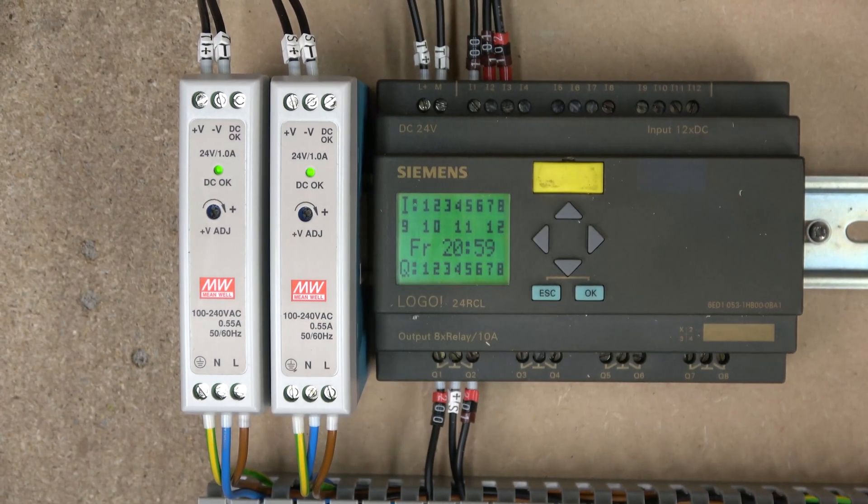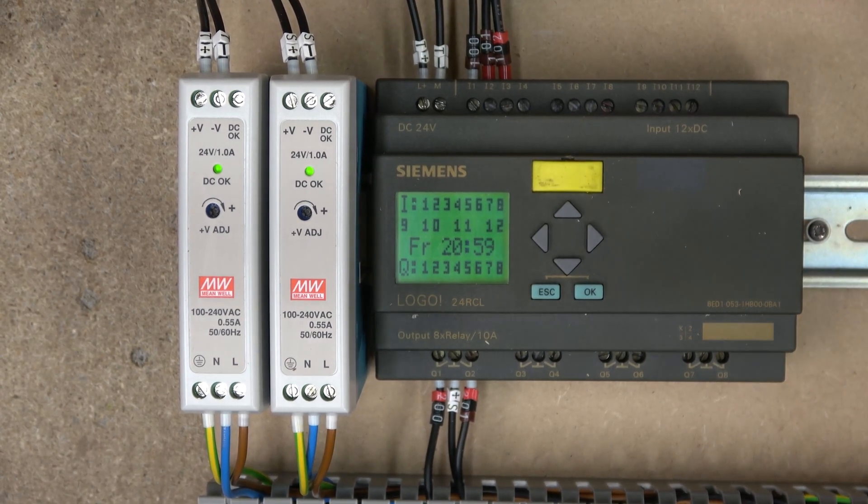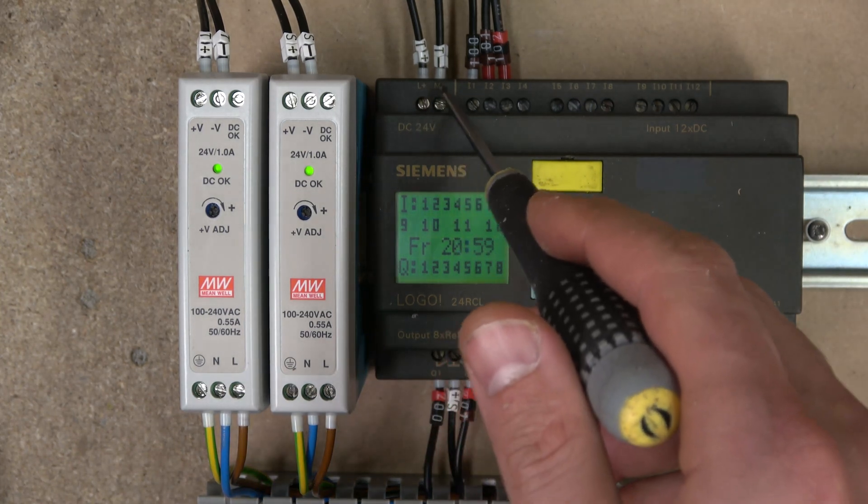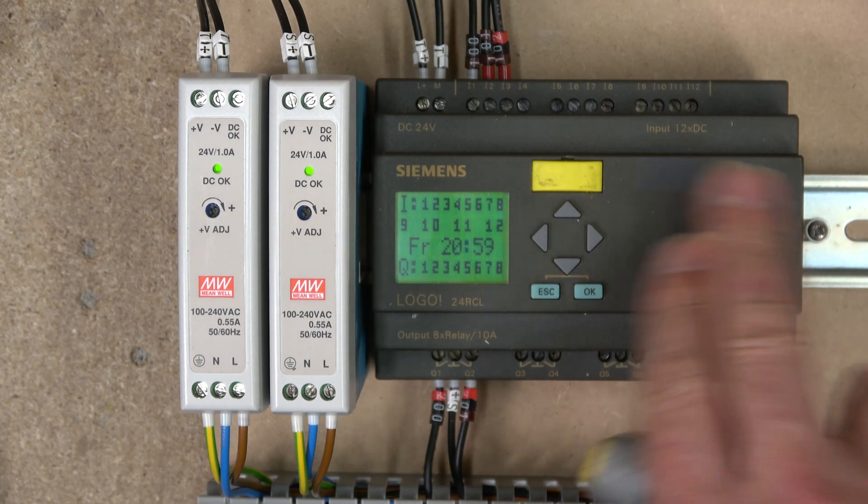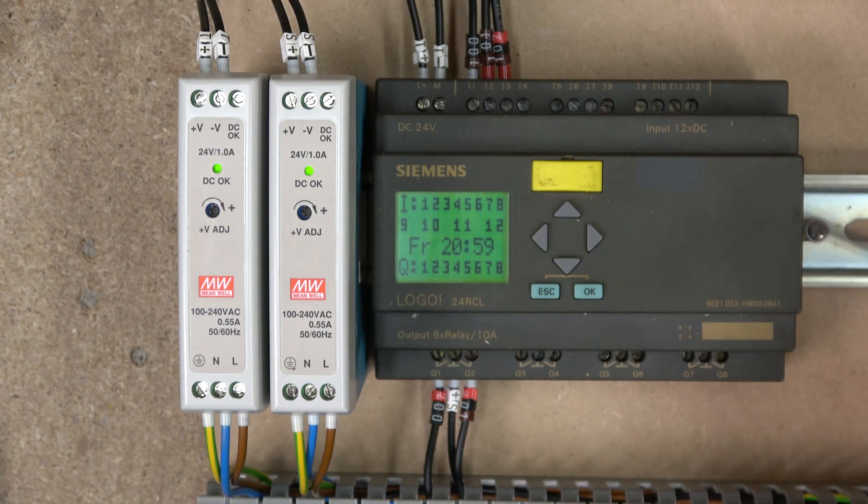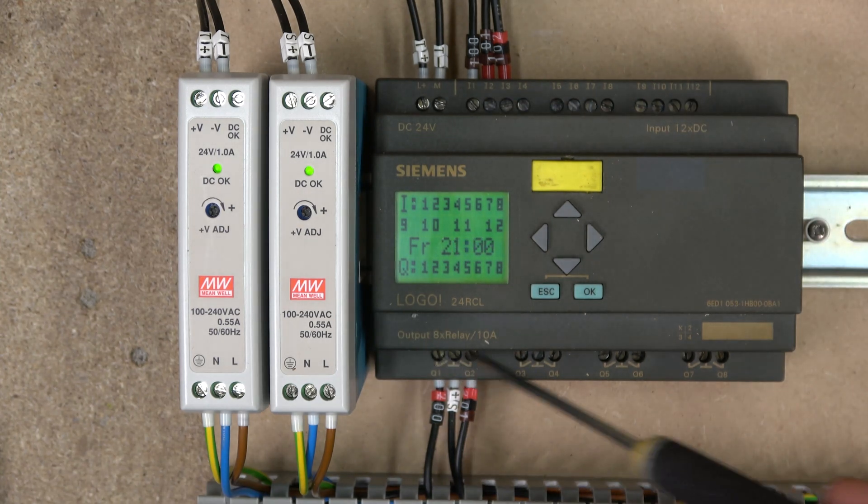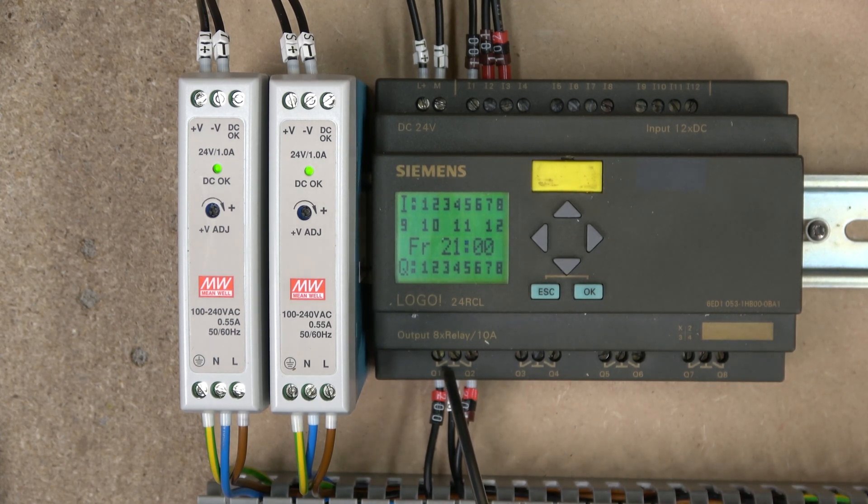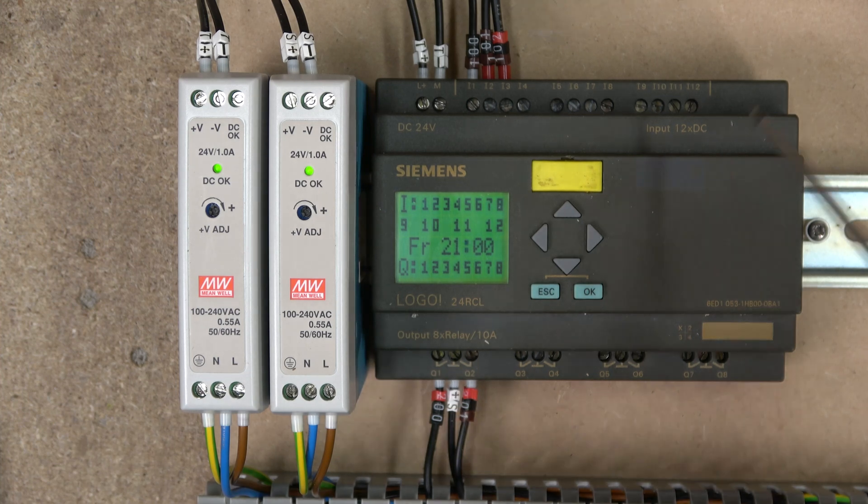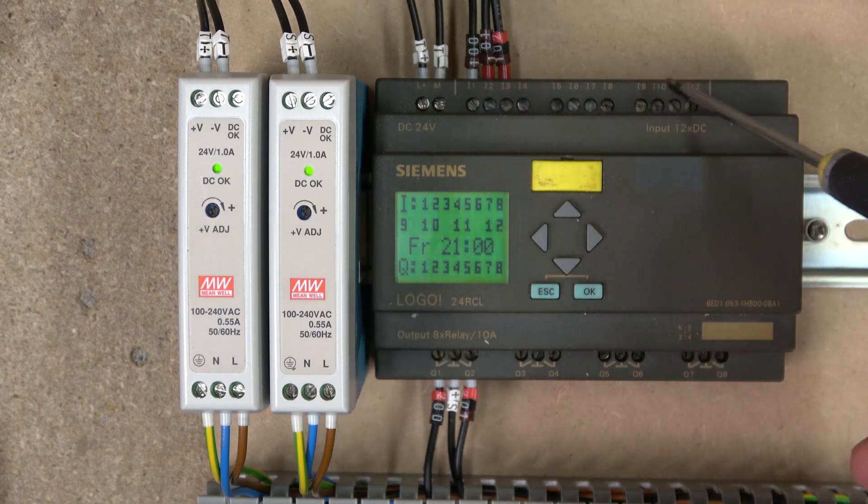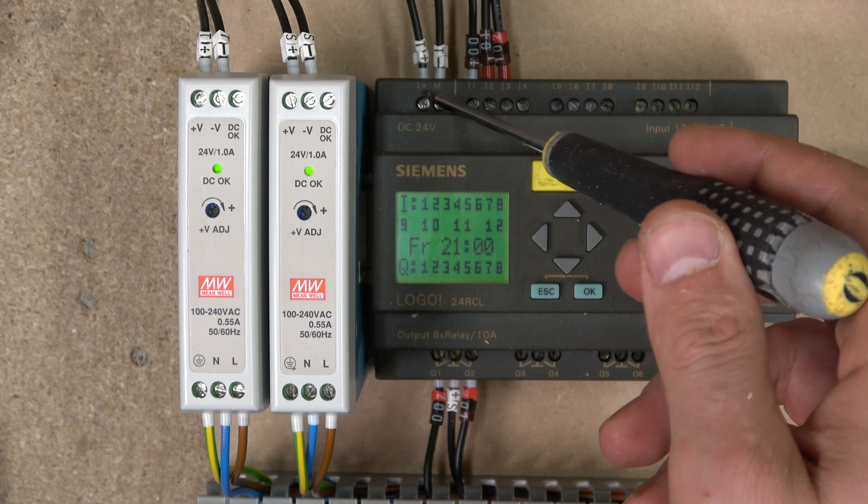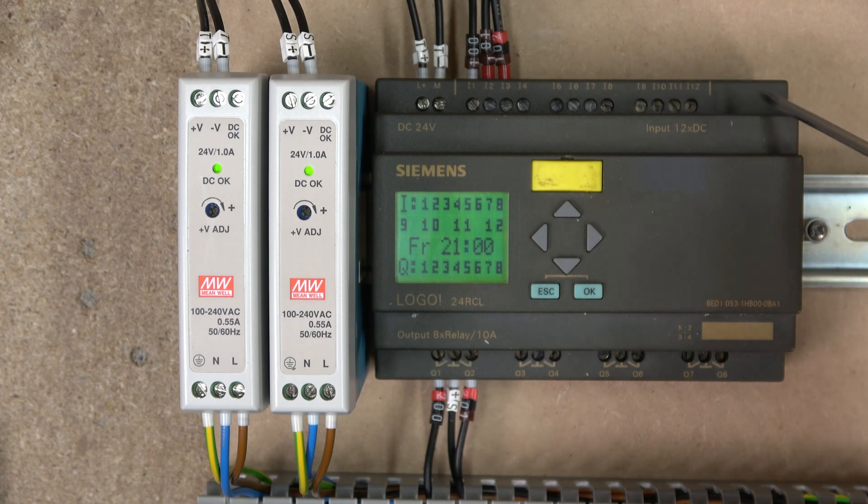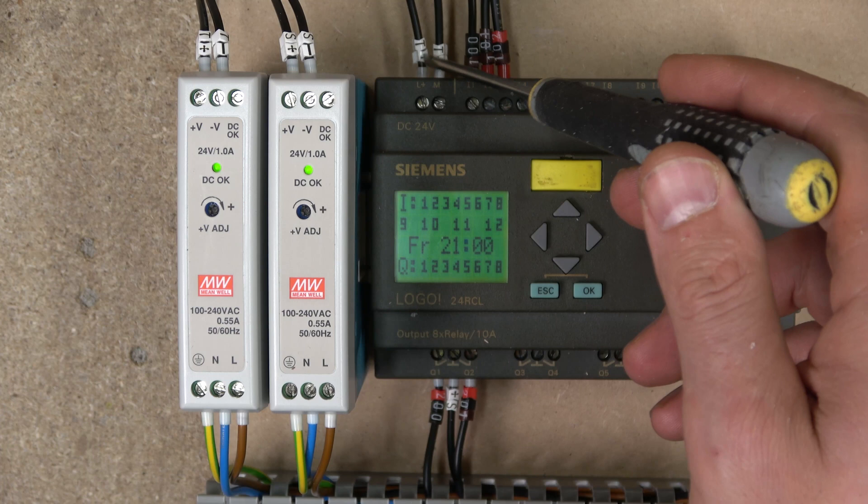Here we are. First thing as usual, I'm going to look at all the wiring and the IOs. The power we have L and N, obviously it's 24 volt DC supply for this controller. The inputs for this controller are in the front and all the outputs are in the back. This is the relay controller. The inputs would usually need a separate supply, but for this controller this supply here is already supplying the inputs, which is from I1 all the way to I12.